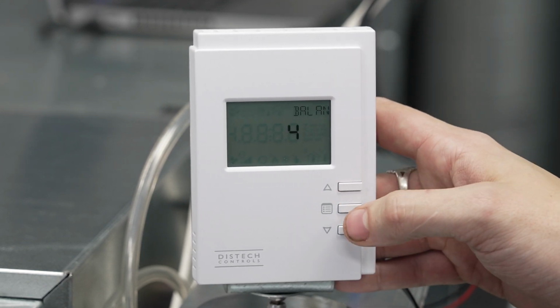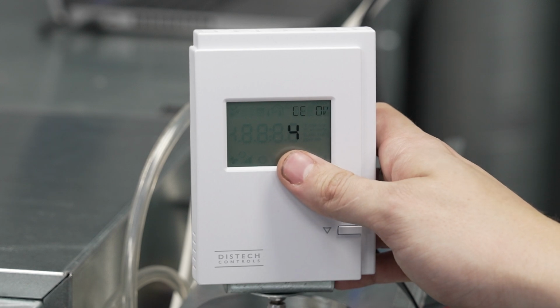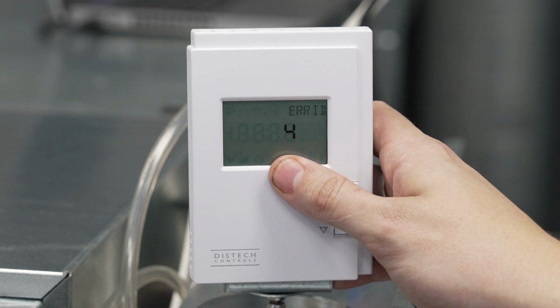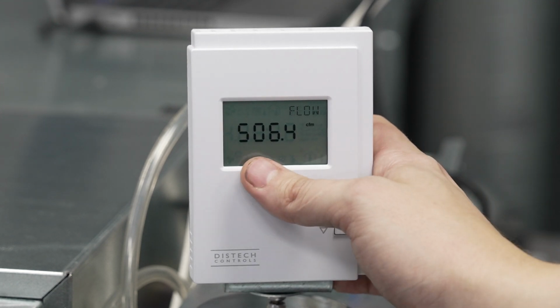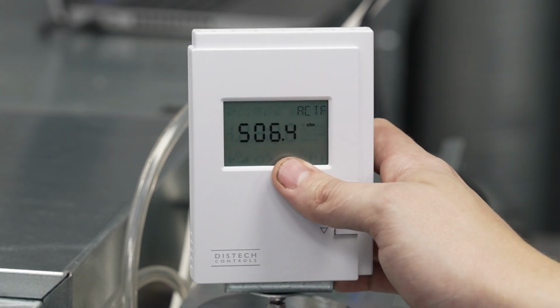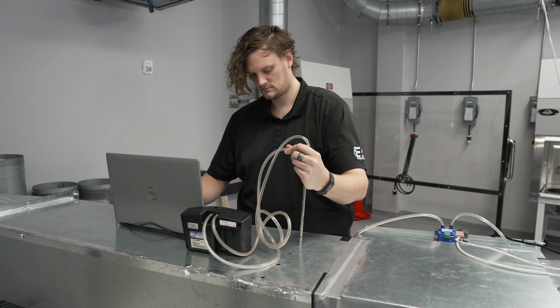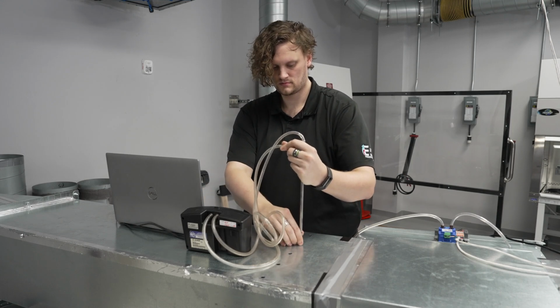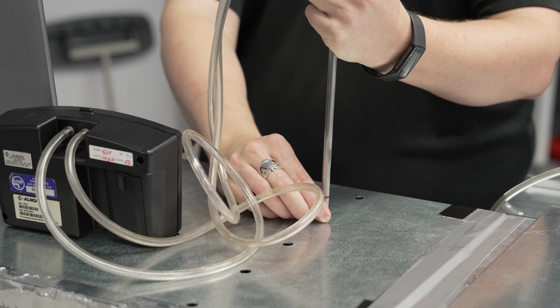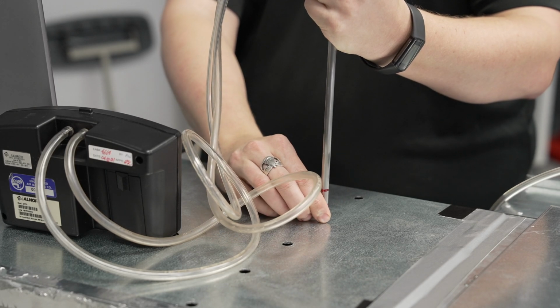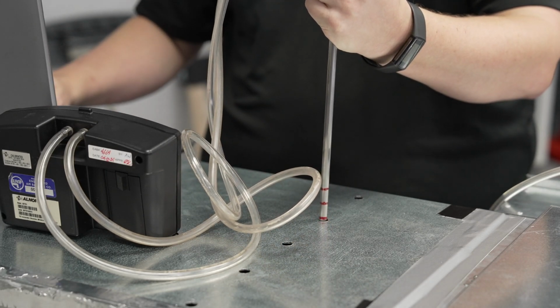Once the VAV has stabilized at its max cooling airflow, we need to know what our actual flow is doing rather than just what the unit thinks its airflow is. And for that, we need a traverse. Per AABC standards, any flow corrections are to be set using an appropriate pitot tube traverse as reference. This will apply both to correcting the VAV airflow as well as the correction factor of the flow hood.